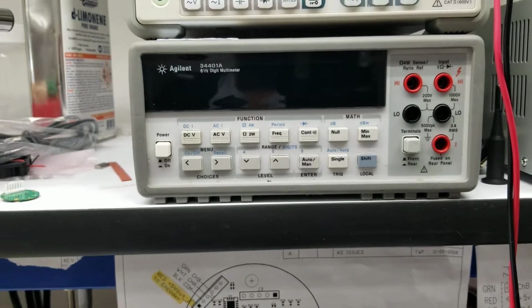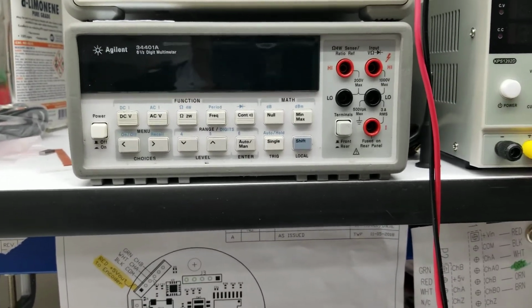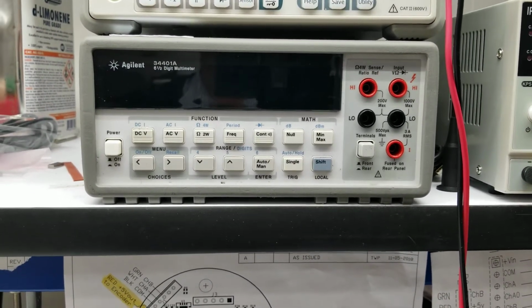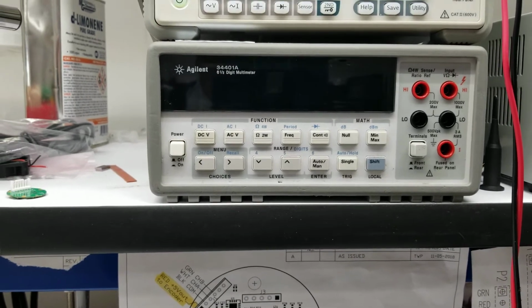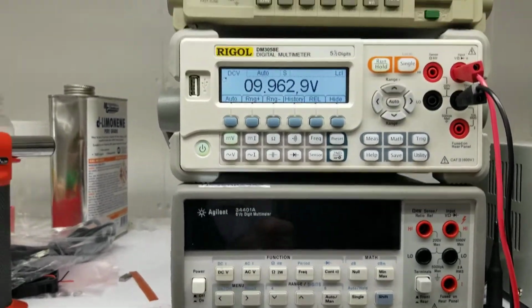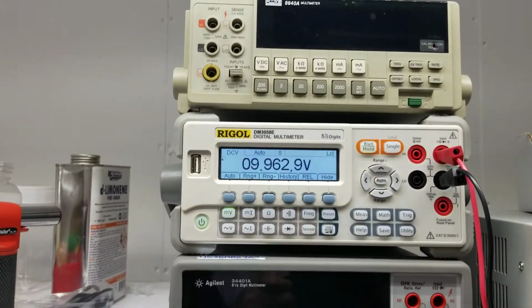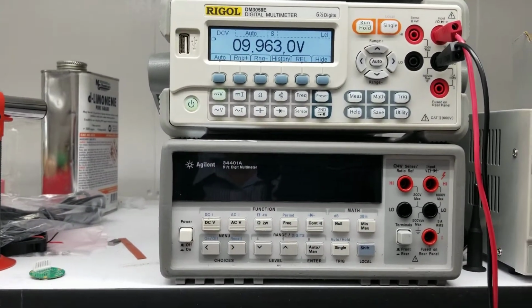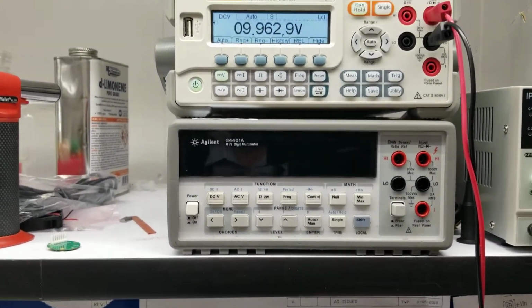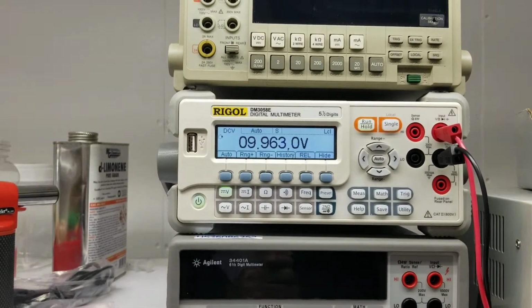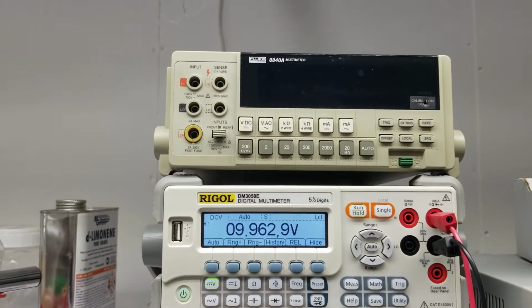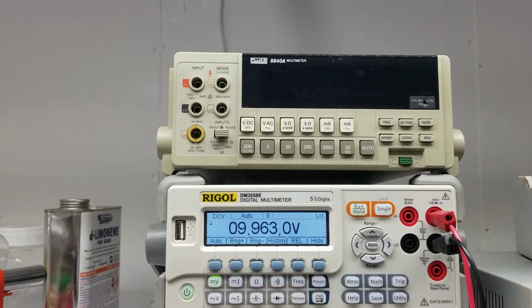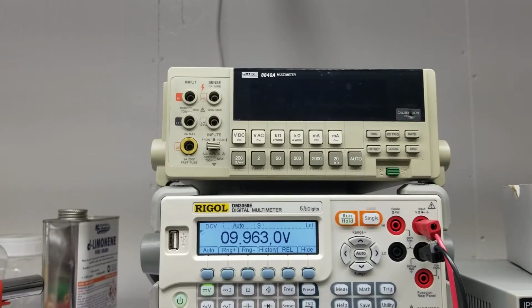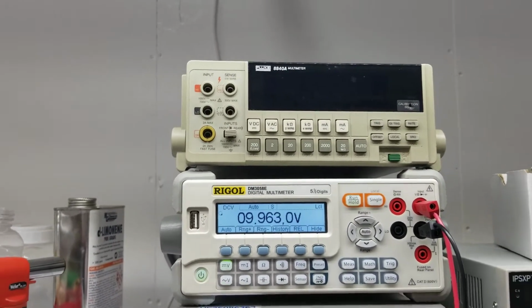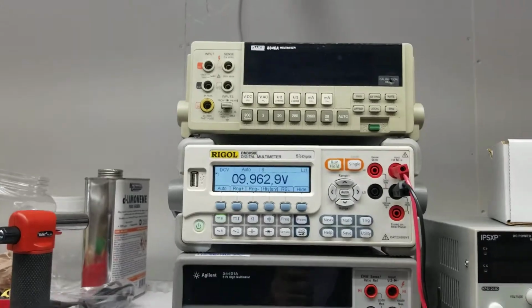This here is an auxiliary unit that we use when we send the others out for calibration, but it's a relatively new meter. And as it turns out, the voltages on these 3 meters are within about 1, maybe 2 millivolts overall when you check it at different voltages. Oddly, I'm really surprised that the Fluke works so well. Since it's so old, the problem with it is the display doesn't show up very well.